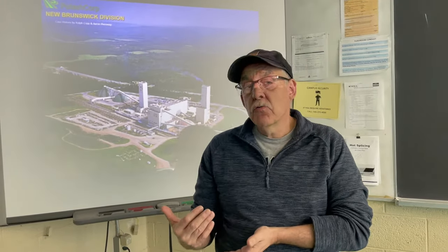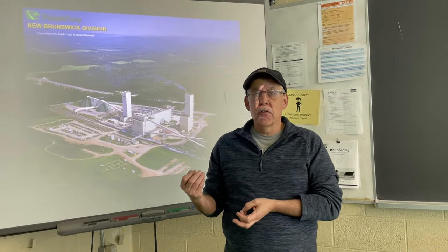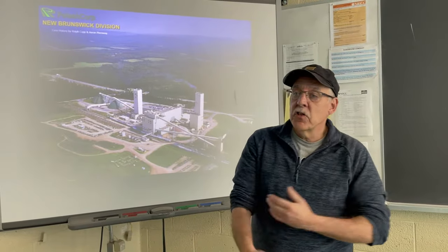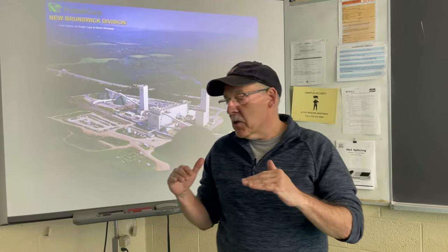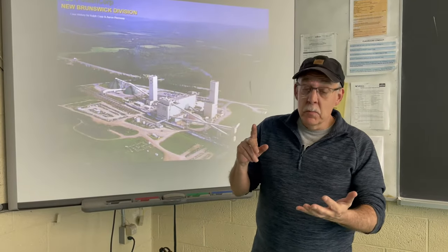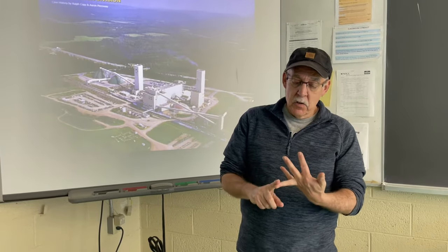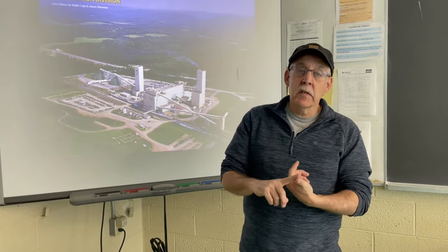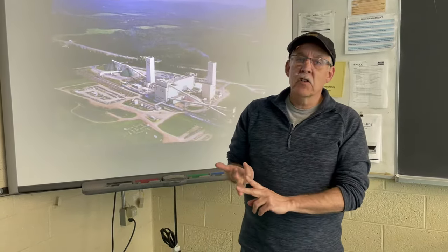And then we also use temperature. If temperature rises, that's usually one of the first indicators that we have a problem with something. All of these technologies are based on a baseline reading. When we put a piece of equipment into service, we assume it's in pristine condition. It's been overhauled, it has new bearings, it has new lubrication, it's been balanced and aligned properly. There's no soft foot, there's no pipe strain. It's running in its optimal condition.